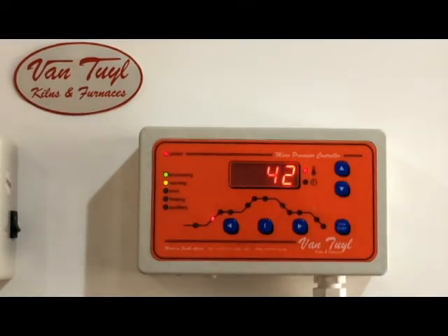in your particular program but doesn't necessarily stop the program and is not a safety concern. To give you an example of those warnings, a power interruption, where perhaps the power has gone off for an hour or two. The VT-36 controller has an automatic restart, so when that power returns, your program will recalculate and will continue on the path of the programs you set. However, it will obviously give you a warning to indicate that it did have a power interruption during your program.